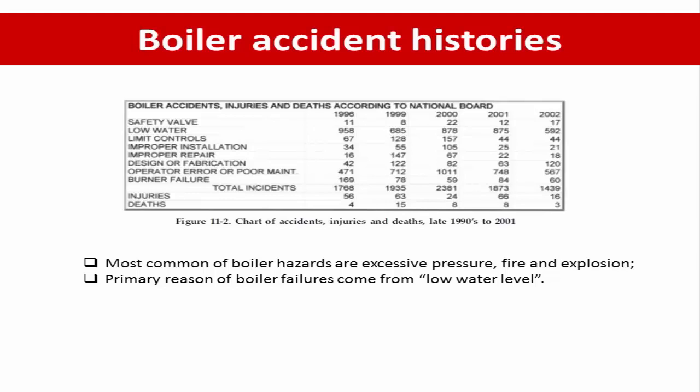Low water level leads to the water level falling low, which can cause the tube to deform and eventually explode. The primary reason for boiler failure comes from the low level, and it shows that about one-third of boiler accidents are caused by low water level.